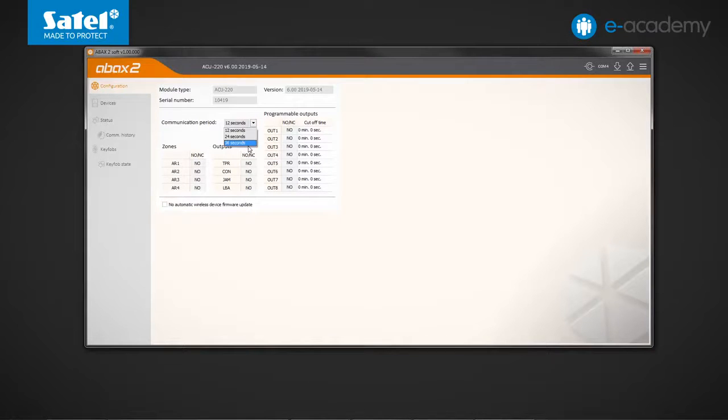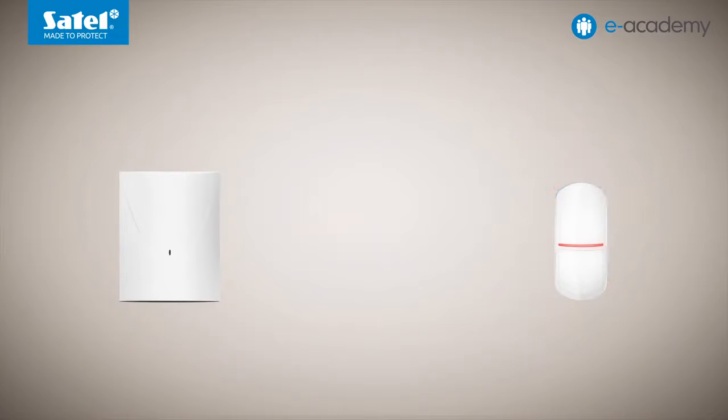In this tab you can set the communication period, which is the time interval at which wireless devices are to communicate with the controller. You can choose an interval of 12, 24, or 36 seconds. During periodic communication, wireless devices send information about their status to the controller, for example about violations, battery status, etc. In response, various commands are sent to the devices, for example relating to the changing sensitivity settings or operating mode of the detectors.